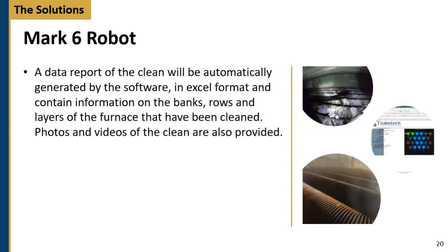So, a report of the clean will be automatically output by the software. I think we've covered some of this before, but it's worth going over it again and reiterating. A report of the clean is automatically output by the software in Excel format and contains all the information on the banks, rows and layers of the furnace that have been cleaned with fan and lance jet, along with photos and videos taken before, during and after the clean.